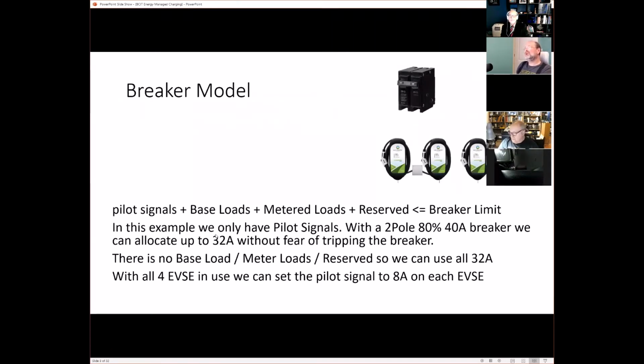So when we get into looking more at what's happening in the building, we look at what a breaker does. Basically the breaker is there to protect the wire. We know that's physically what it's there to do. In the software world, I'm trying to make sure that breaker never trips. A 40 amp breaker is normally listed as a 2-pole 80% 40 amp breaker, which means it takes 2 lines in. It can operate at 80% of 40 amps continuously, which means 32 amps. And so that's how we know that we can offer up to 32 amps, and we don't have to worry about that tripping the breaker as long as the breaker is not old and defective.